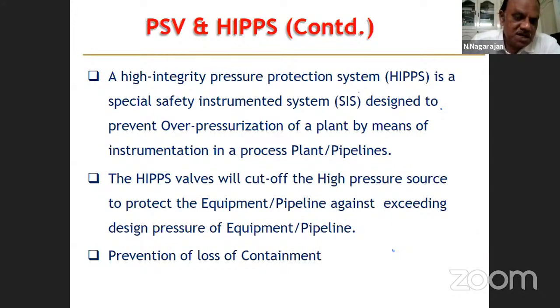Then if there is no protection in the inlet, your plant will see 100 bar pressure. All the equipment will fail because we have designed the plant for 25 bar pressure. If suddenly a very high voltage comes into the house, okay, instead of 230 volts, if you suddenly get 350 volts, 400 volts, all your electrical system will fail. All the electrical equipment will be damaged. This is something similar to that.